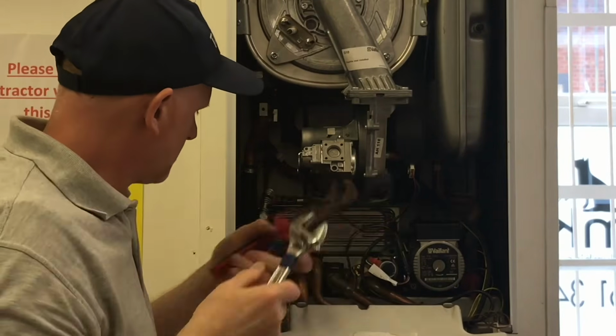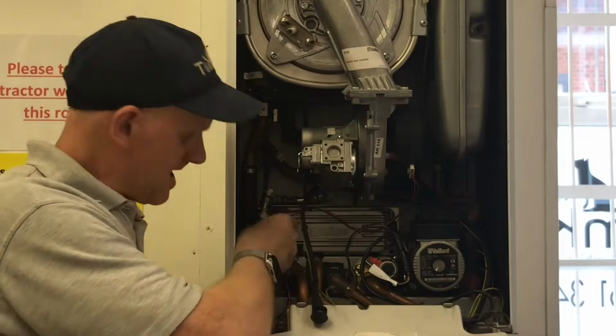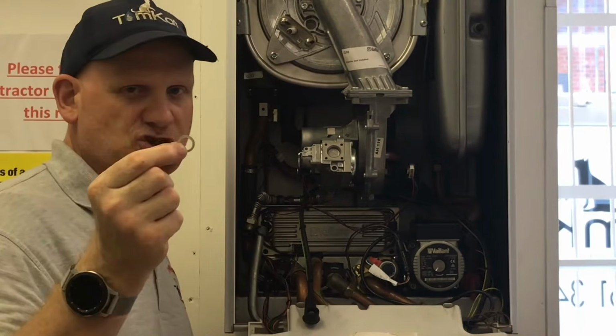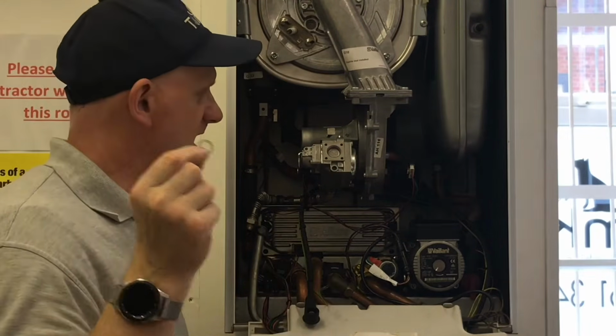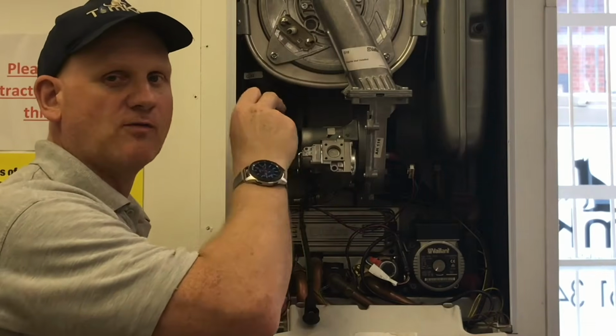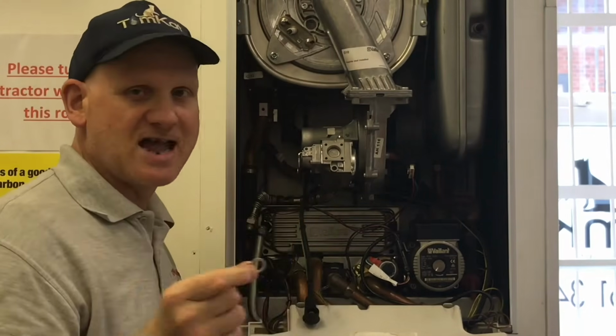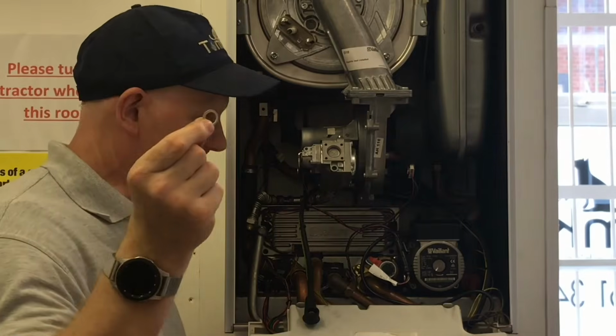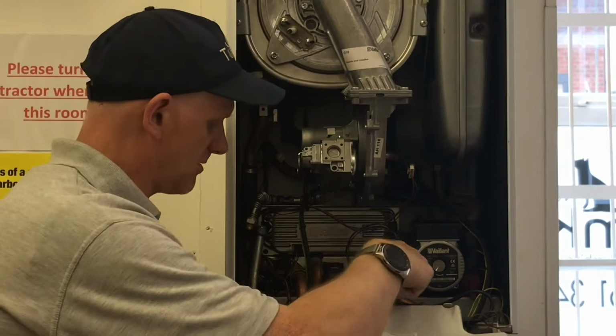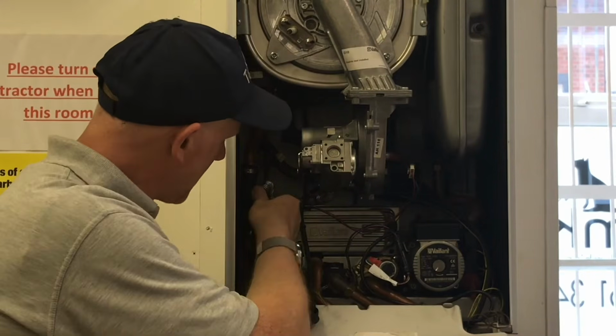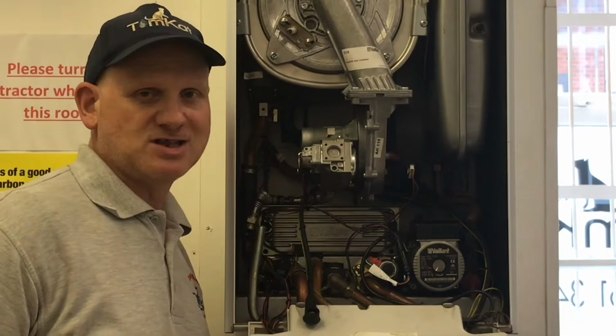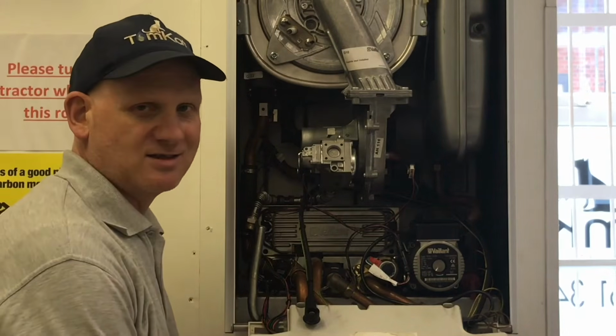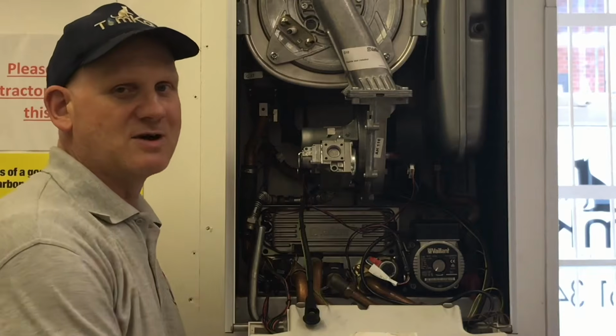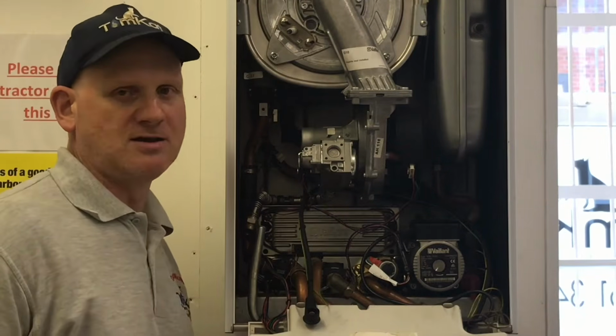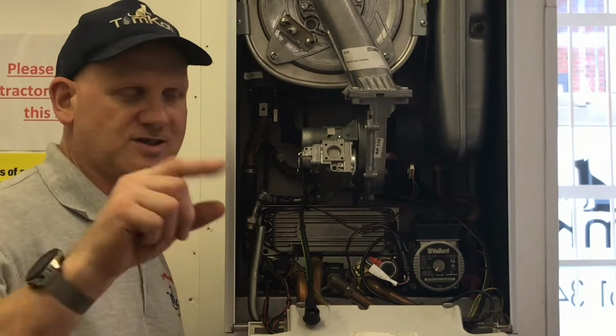We'll just undo them. And then inside here is a washer. This washer will actually need to be replaced every time you take the burner door cover off, or every time you break this connection. So this does come in the kit when we do replace the burner gasket. So that is the gas connection disconnected. The gas is not connected to this appliance, but you would need to isolate it down at the bottom here. Okay, there is an isolation underneath, you'll see that soon.